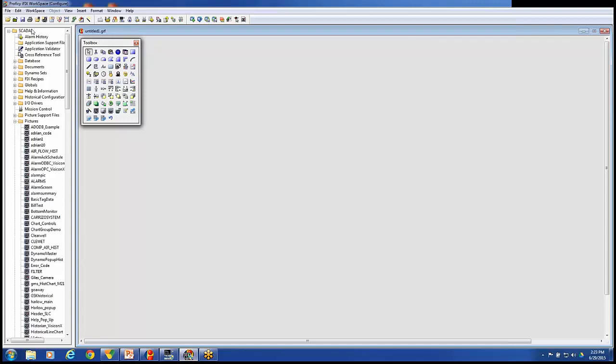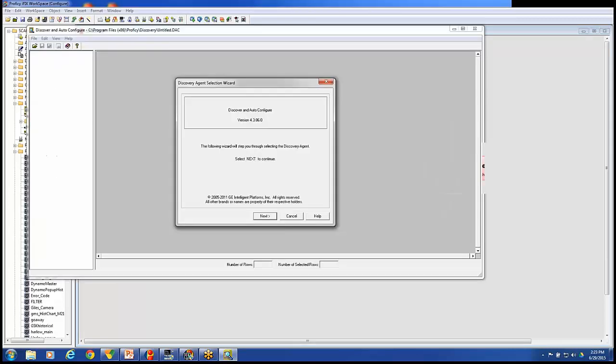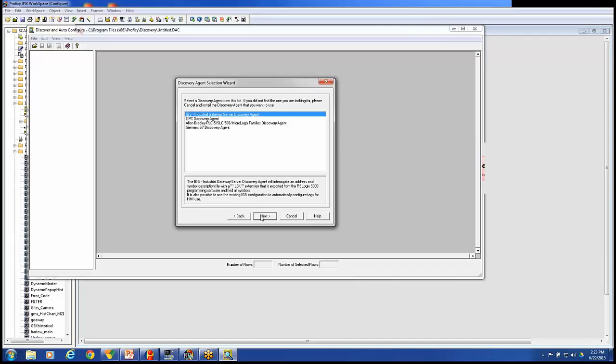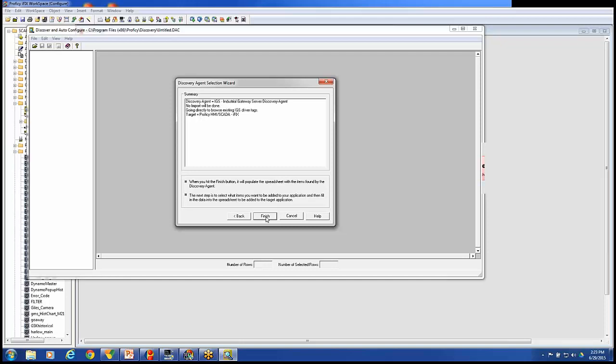In the workspace in our system tree, under IO drivers, there's the Discover and Config tool. We're going to launch that. We'll hit Next. We're going to use the IGS driver discovery agent as our agent to provide us information from our PLC. I could have exported out an L5K file from my RSLogix. But instead of doing that, we're just going to browse the current PLC. So I'm going to use the IGS driver to reach into the PLC and browse the current tags in there. Hit Next and Finish.